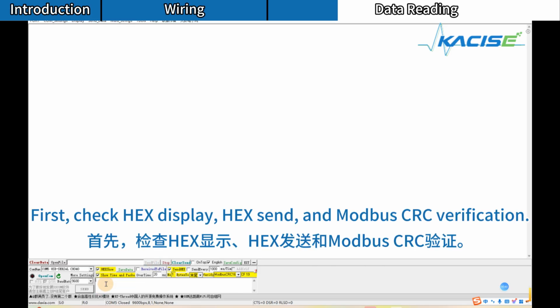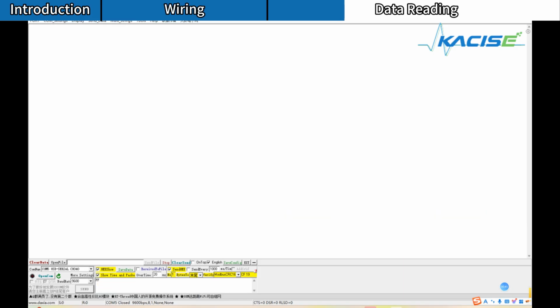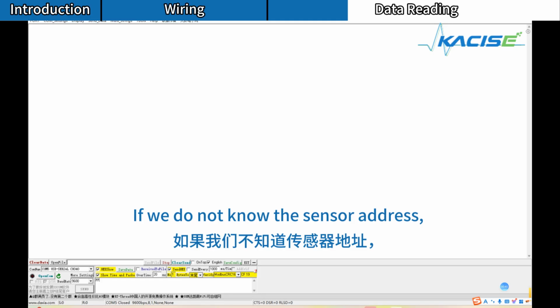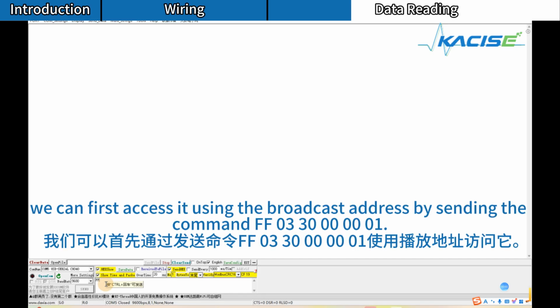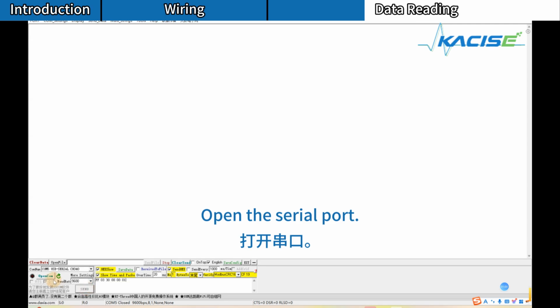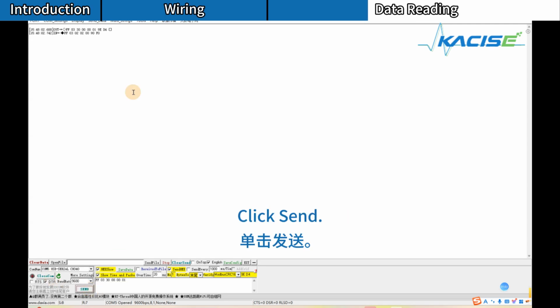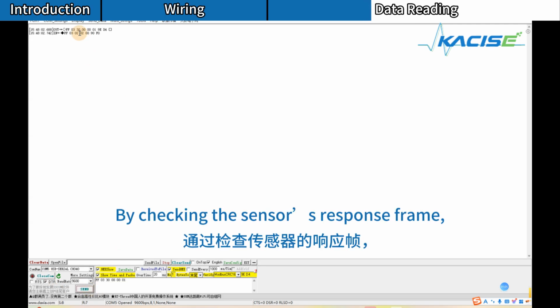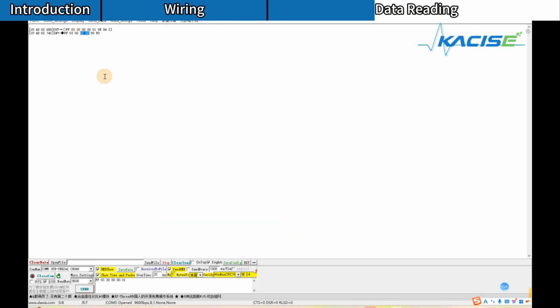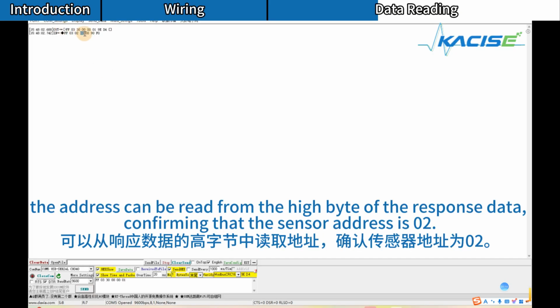First, check hex display, hex send, and Modbus CRC verification. If we do not know the sensor address, we can first access it using the broadcast address by sending the command FF0330000001. Open the serial port. Click Send. By checking the sensor's response frame, the address can be read from the high byte of the response data, confirming that the sensor address is 02.